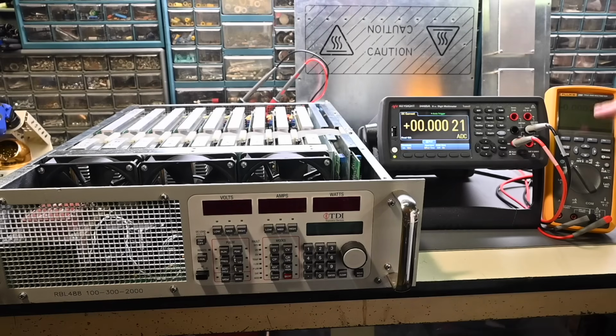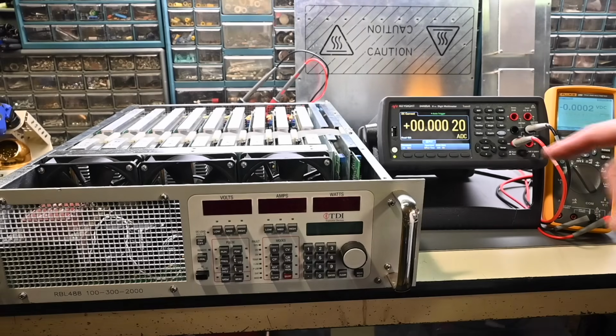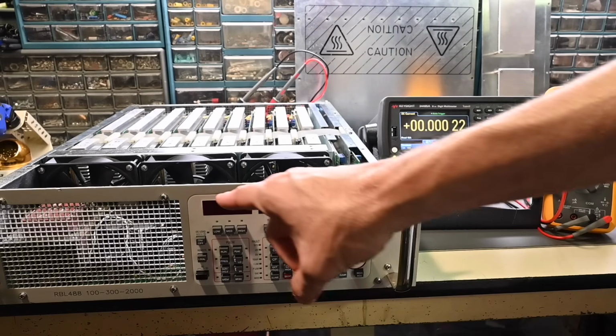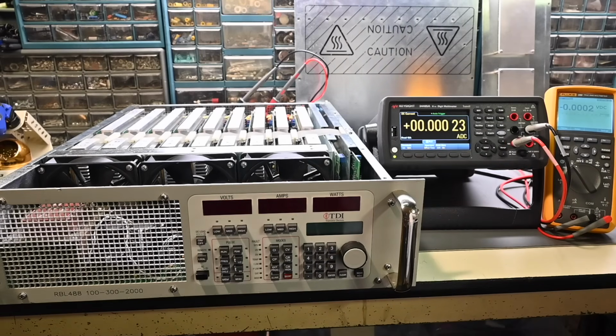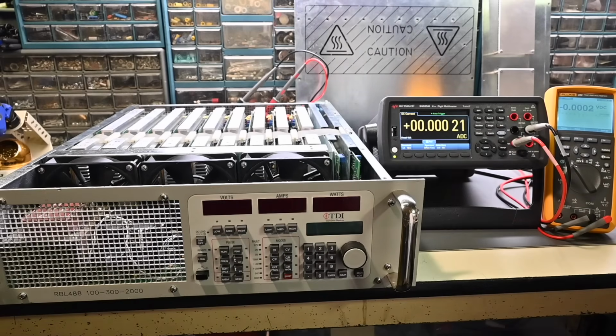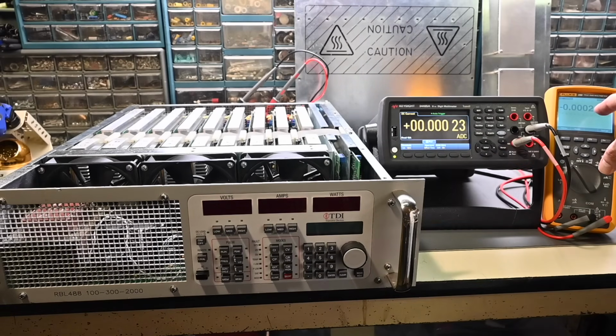Now, this voltmeter, let me turn the backlight on here, the Fluke 289, is connected across the terminals on the back of the electronic load. So this voltage should match this voltage, and of course that's what the power supply will be set at. I'll set it to 40 volts, that'll be a good test voltage. But as I draw more current, then this voltage will drop because there are some losses in the test cables and the test leads. So this voltage and this voltage will drop down, that's normal, but they should remain basically the same in value, together, but they'll fluctuate a little bit under load.